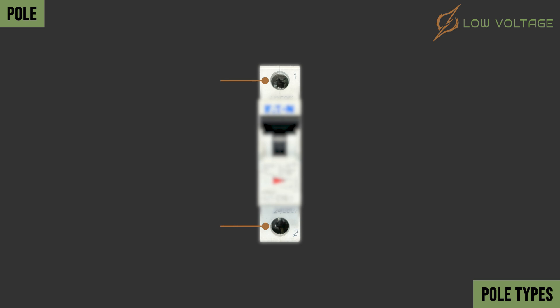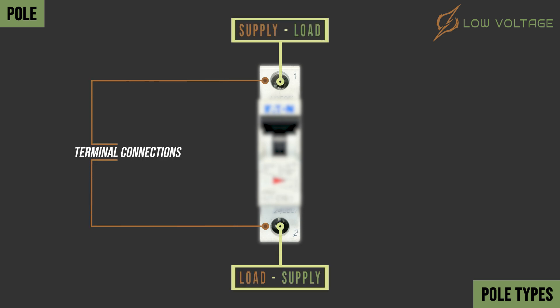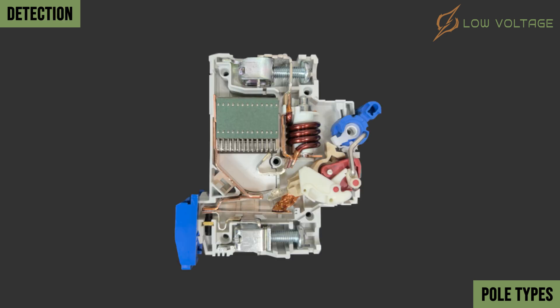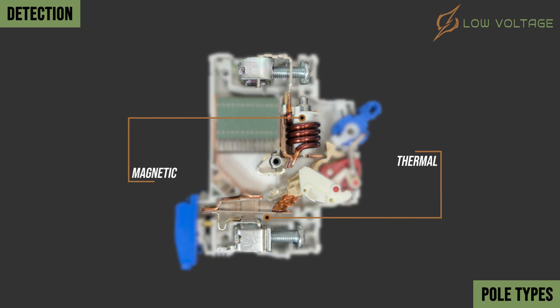A pole is simply linked to the wiring connections through the screws, and where the line is connected to the MCB. So when we find two screws opposite to each other, then we have found the pole of the breaker. Detection is the ability of a pole to detect electrical faults, like overload and short circuit. This is achieved by the thermal and magnetic units that are installed between the connecting screws of the MCB, which is also referred to as the pole of the MCB.